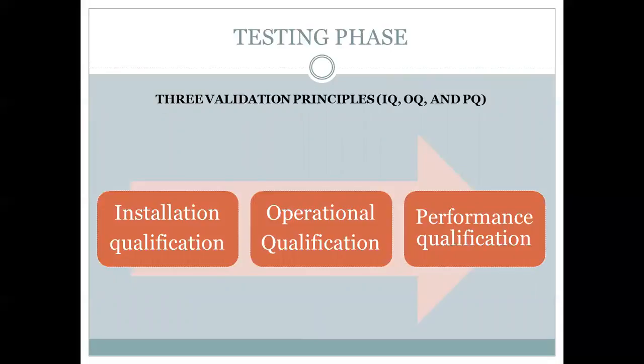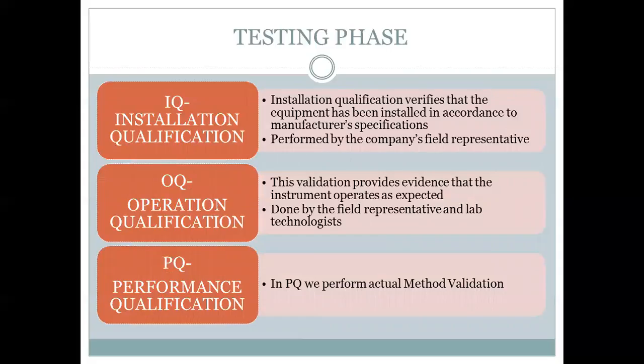So in the testing phase, we have three validation principles: installation qualification, operational qualification, and performance qualification. Installation qualification verifies that the equipment has been installed in accordance with the manufacturer's specifications, and this is performed by the company's own field representative. Operational qualification provides evidence that the instrument operates as expected, and it is done by the field representative of the company as well as the lab technologist.